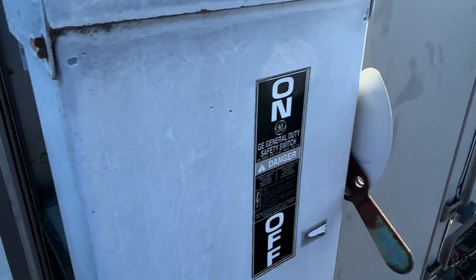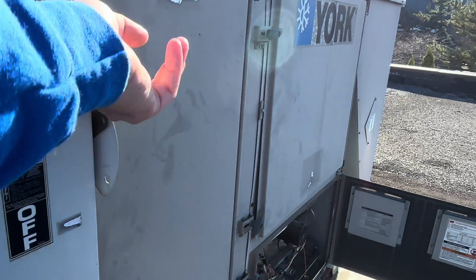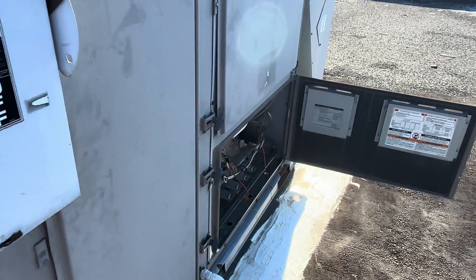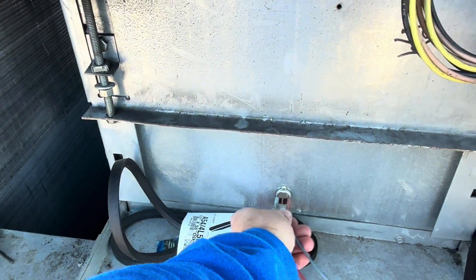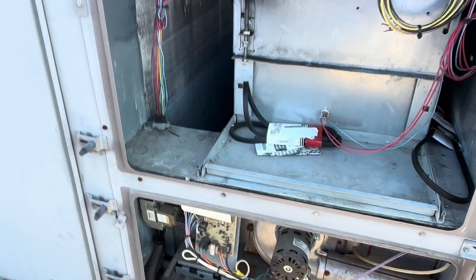Resetting that satisfied our furnace control. This one's still in a nine-flash so we'll have to reset power and figure out why that limit switch tripped. That switch is like an overheat sensor — a lot of times it'll trip if you have a clogged filter or a loose belt, which it's not.